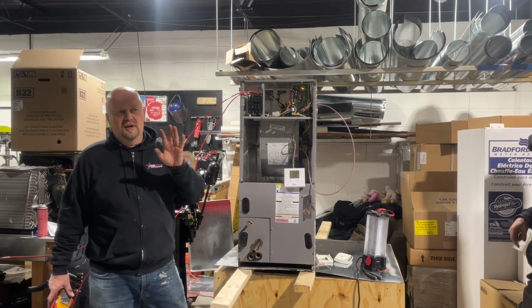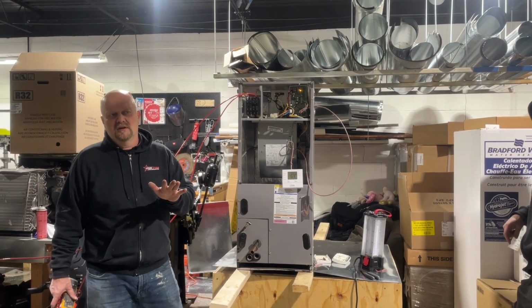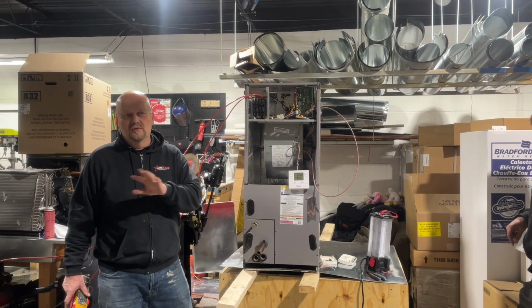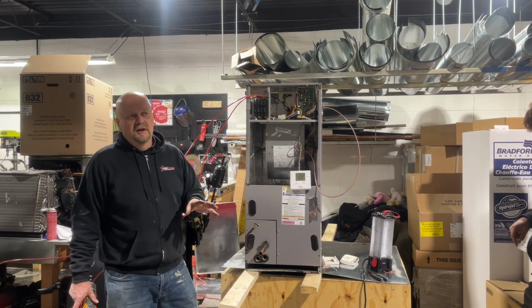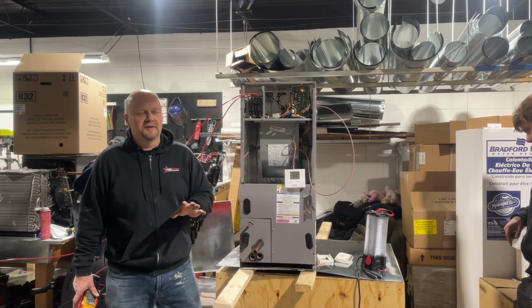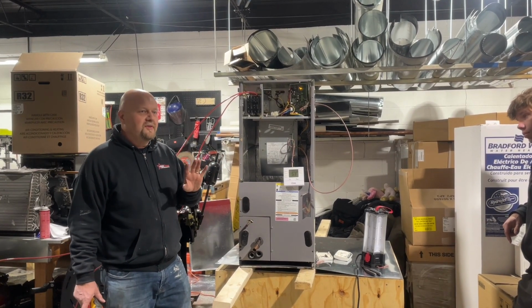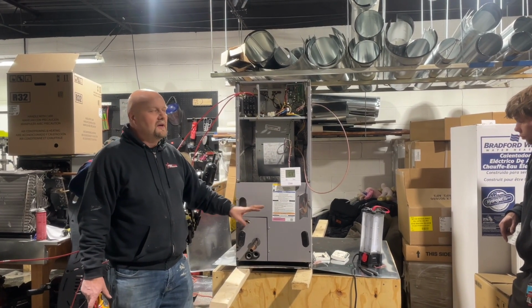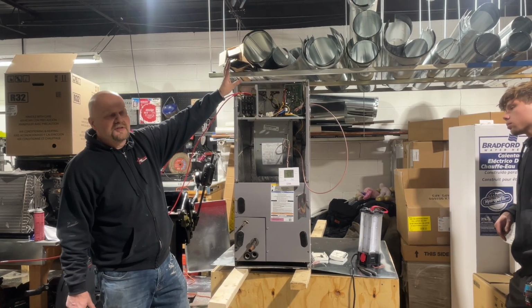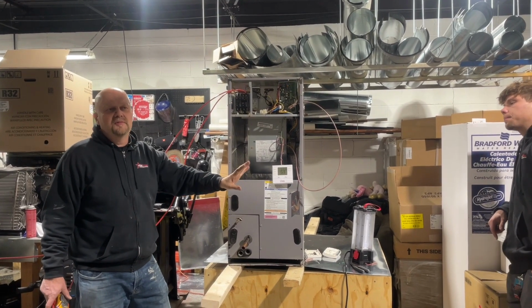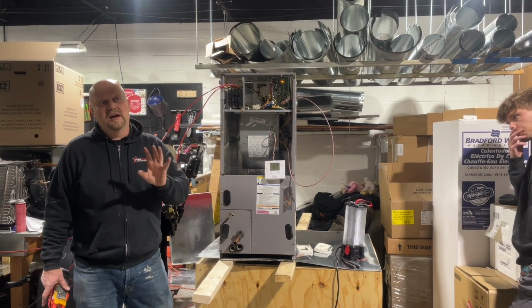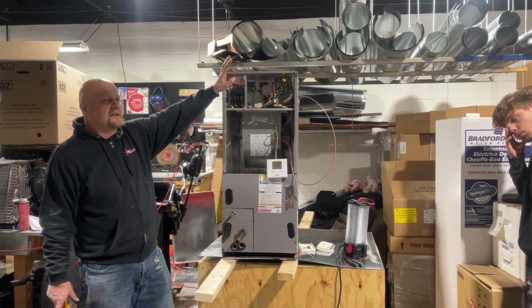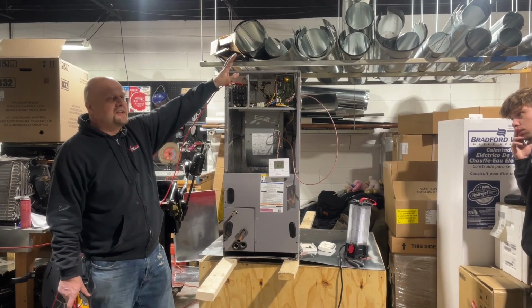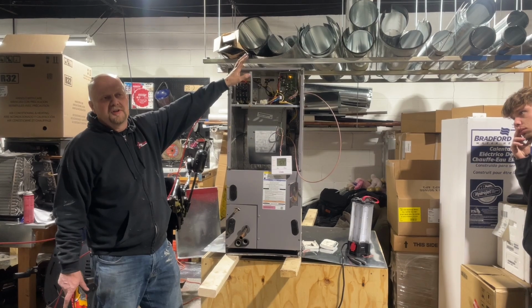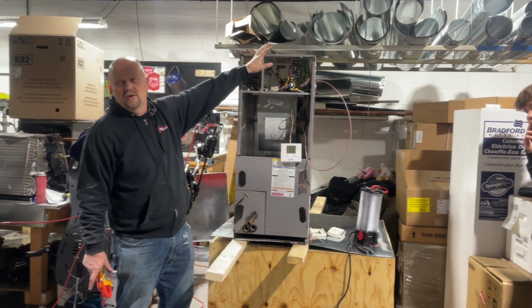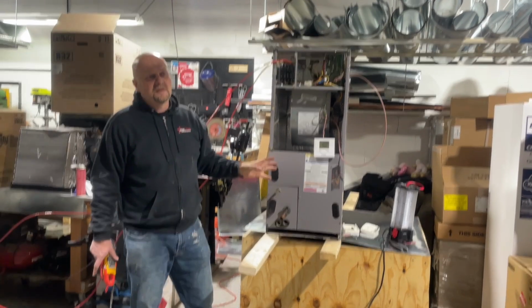When we do those gas furnaces combined with the heat pump, or Peter calls them dual fuel applications, that's when we cannot run them at the same time, because the source of heat is on the bottom and the coil sits on top of the furnace. So if you turn both of them on at the same time, you'd be running really hot air across the coil, which in a heat pump application is a condenser coil, right? Normally it's an evaporator coil, but in the heat pump that becomes a condenser coil. That would overheat the condenser.